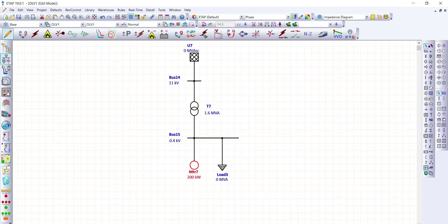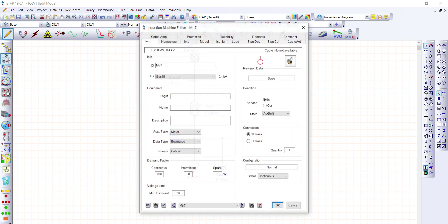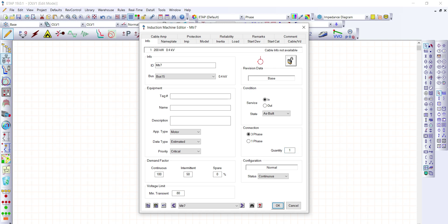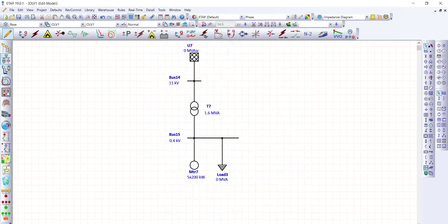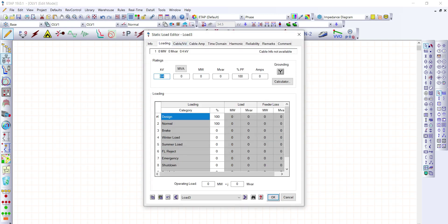We can also specify the number of motors on this bus. Let's say we have five motors of the same 200 kilowatt rating — enter five here. So now we have five times 200 kilowatt. For the static load, from the loading tab we assign approximately 0.4 MVA.